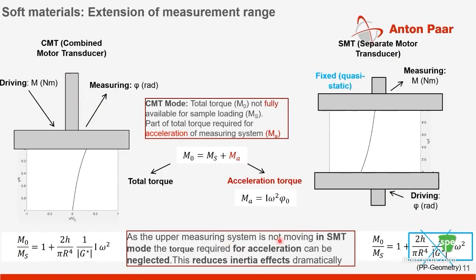Now, in order to extend the frequency range, typically people do frequency sweeps carried out at a bunch of different temperatures, and people do something called time temperature superposition to extend the frequency space. This broadening of the usable temperature and frequency range is very useful and of high interest to people. But you also need to worry about some challenges, right? At very low temperatures the material is very stiff, so you need to exactly compensate for the torsional compliance in the system. At very high temperatures you need to worry about softening of the sample, and at high frequencies there could be inertial effects, which we saw earlier. So you need a controller which can control both these entities very well.